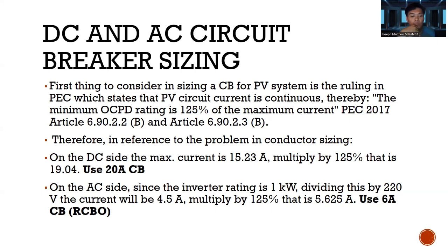Titingnan natin, hindi eksakto yung computation natin. Kunyari, hindi siya naging eksakto ng 20 ampere. Ayun, sabi nga dito, 19.04. So pwede na tayong gumamit ng 20 amperes for that current. Gagamit na tayo ng 20 ampere CB na wire. So on the AC side, since the inverter rating is 1 kilowatt, dividing this by 220 voltage, the current will be 4.5 ampere multiplied by 125%, that is 5.625 ampere. Use 6A CB RCBO. So yun nga, kung mapapansin natin, hindi eksakto ang mga bilang natin ng current sa gagamitin natin na wire. Di ba? So, pwede tayong mag-approximate diyan. So, kunyari, 5.6, pwede na tayong gumamit ng 6 amperes.